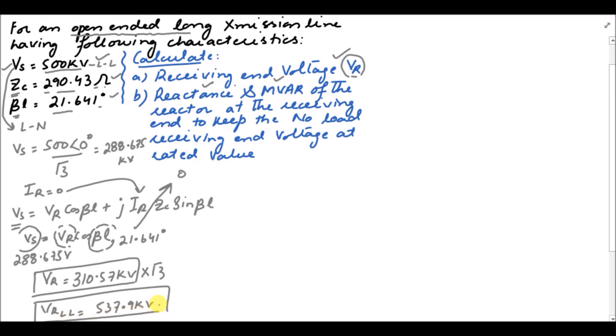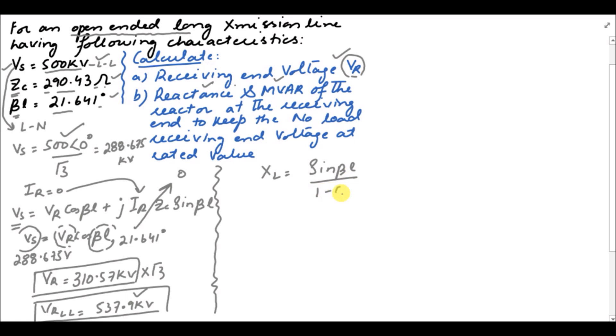So the receiving-end voltage when the line is open-ended is 537.9 kV, while the sending-end voltage is 500 kV. This confirms the Ferranti effect — there is increased voltage at the receiving end, approximately 37–38 kV above nominal. To reduce this voltage to the nominal value, we use the formula XL = Zc·sin(βl) / (1 − cos(βl)), with βl = 21.641° and Zc = 290.43 ohms.